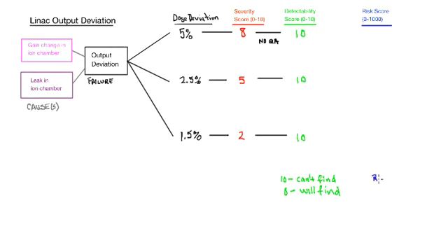Okay, so then finally you get this risk score, overall risk, and that's the severity times the occurrence. I didn't talk about occurrence, but let's go back here to the cause area. So occurrence is how often such a thing would occur. For now, let's give it a 10. It's just an example here. So we know it definitely happened. And then you multiply it by the detectability. So the maximum score is 1,000 that you could get here.